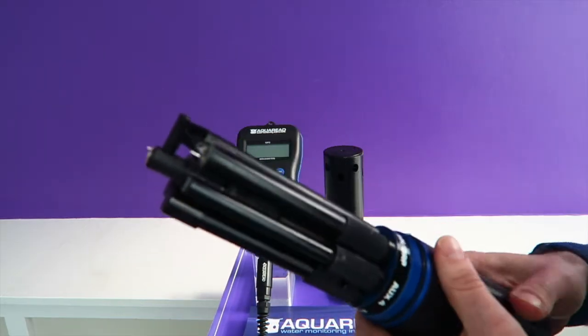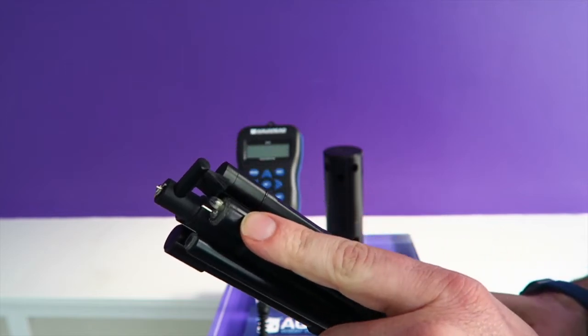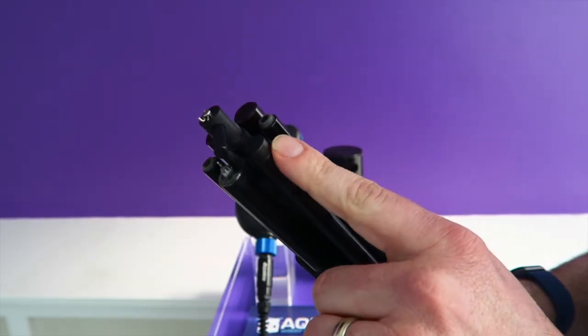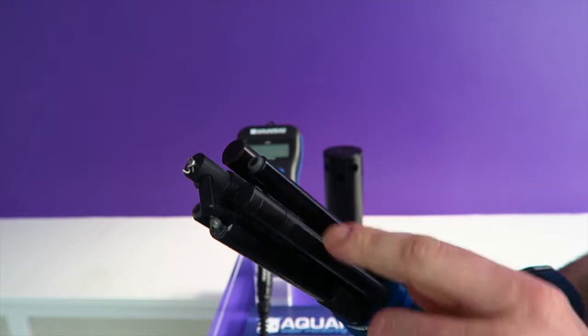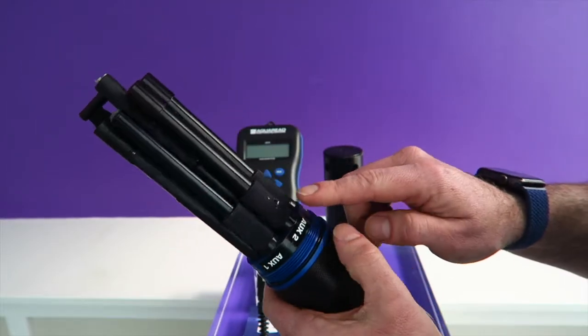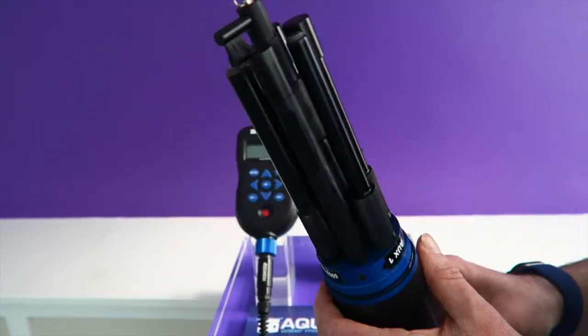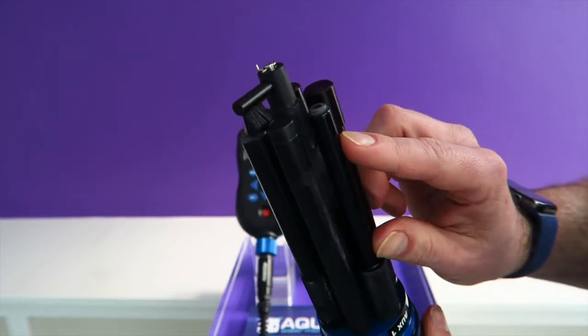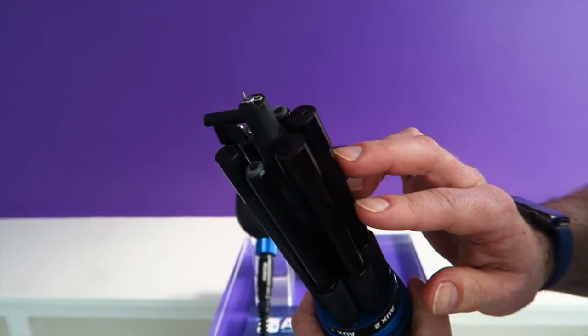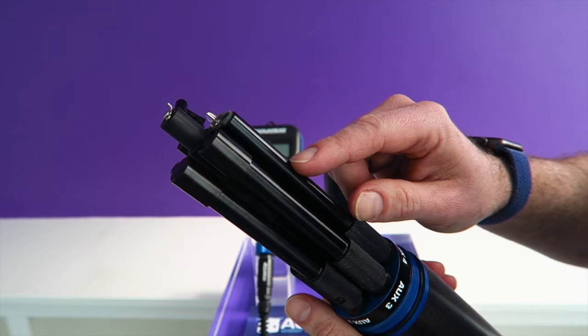On the probe we have the combined pH ORP sensor, optical dissolved oxygen, and conductivity on the inside. We also have 4 auxiliary ports for adding additional sensors. Here we have an ion selective sensor, here we have 2 optical sensors, and again another ion selective sensor here.